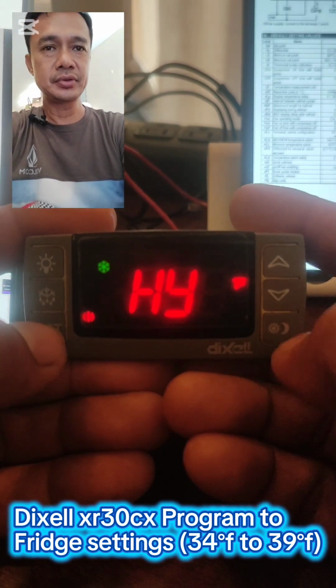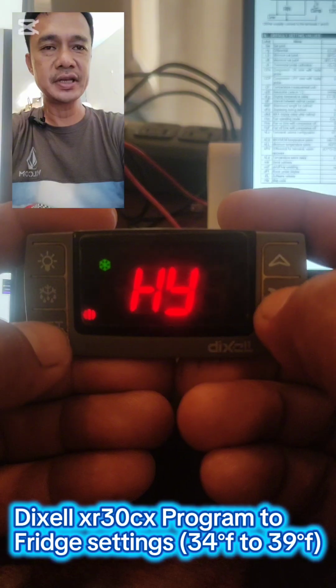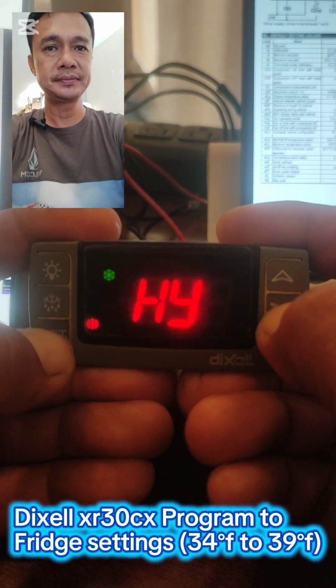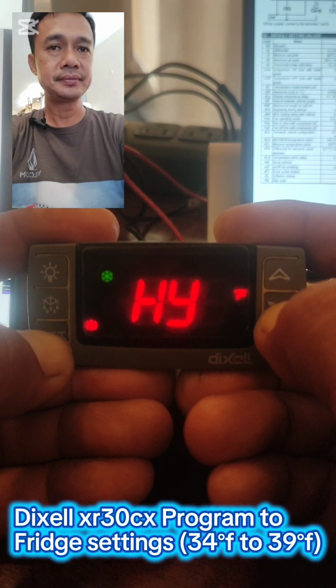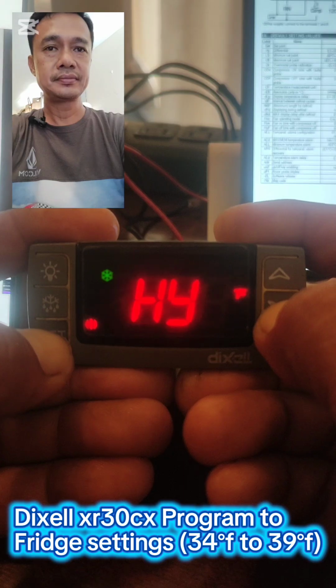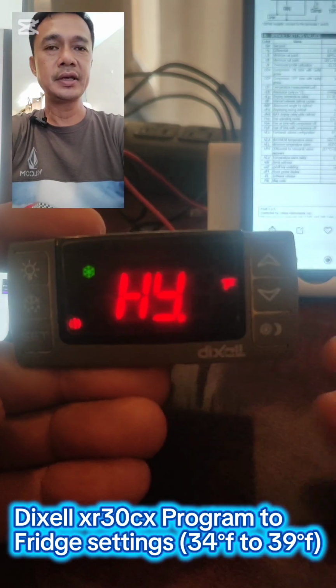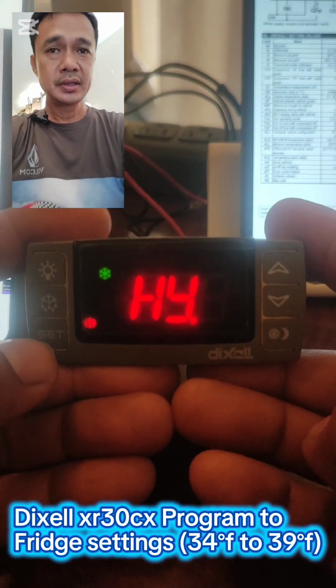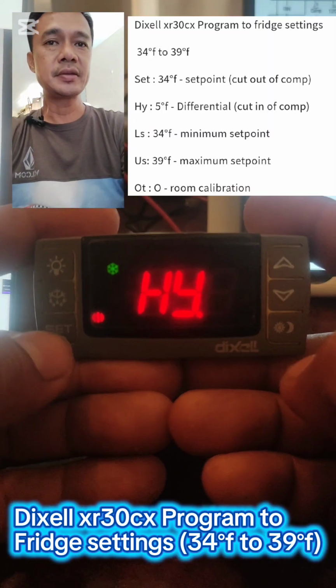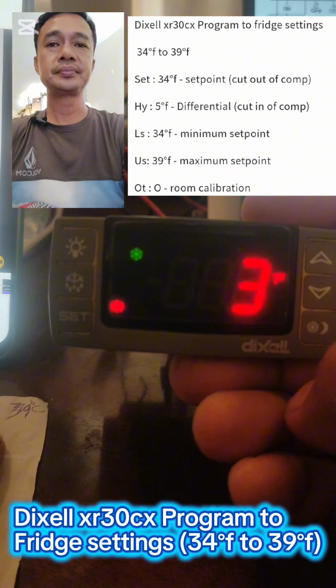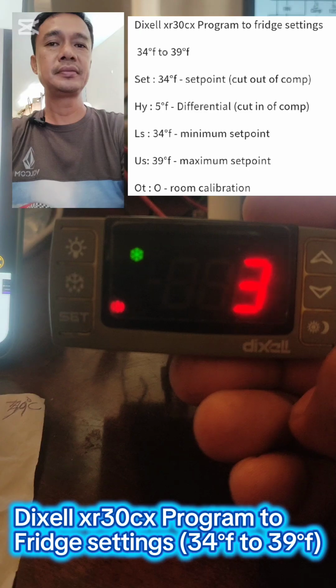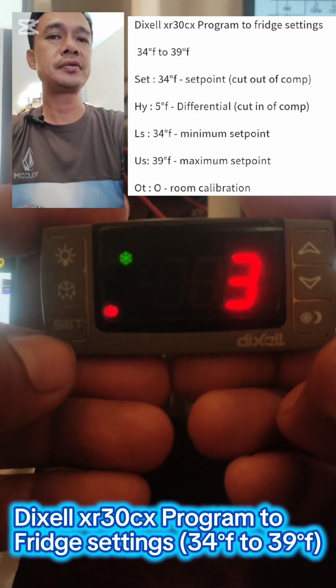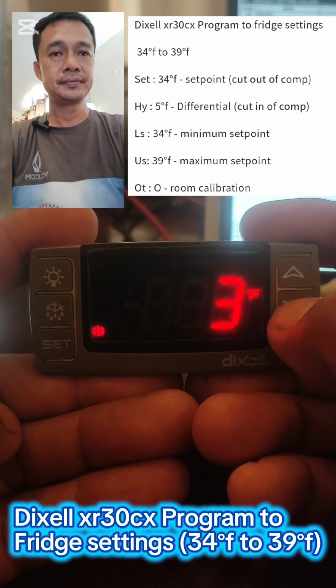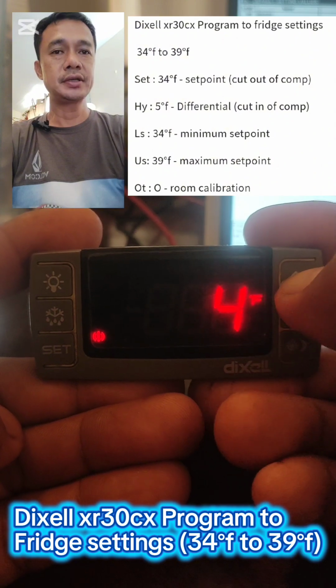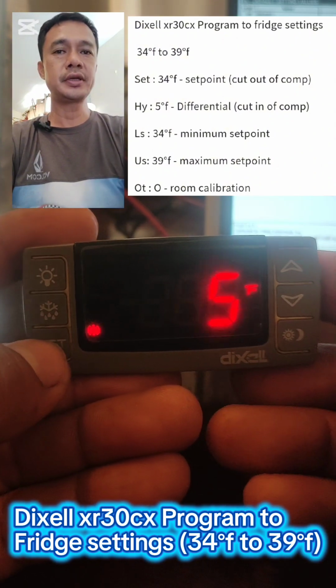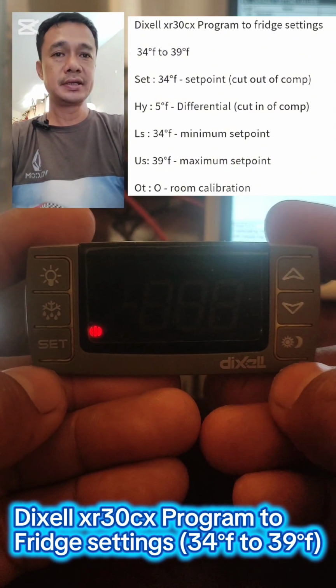And another set button and down button for 7 seconds to enter the hidden parameter. Just long press it. And there, release. We're going to change the differential. 39 minus 34 is 5. So we're going to change 3 into 5 by pressing the up button here. Then press set to memorize.